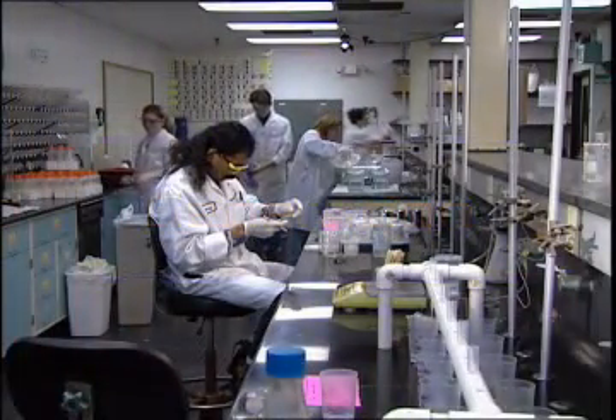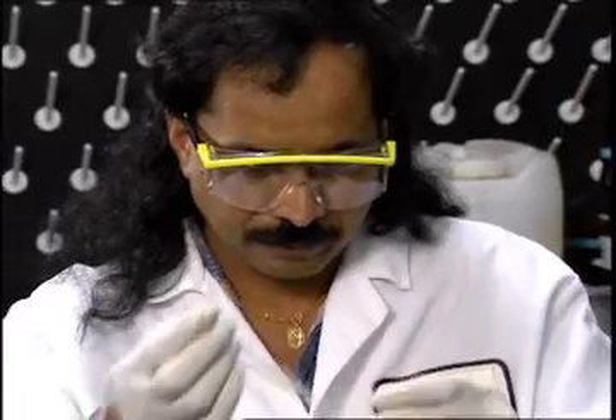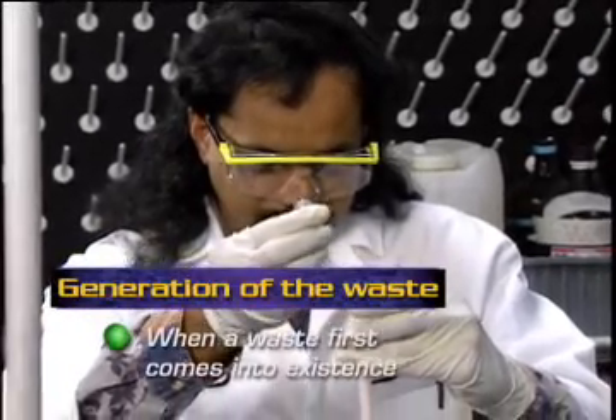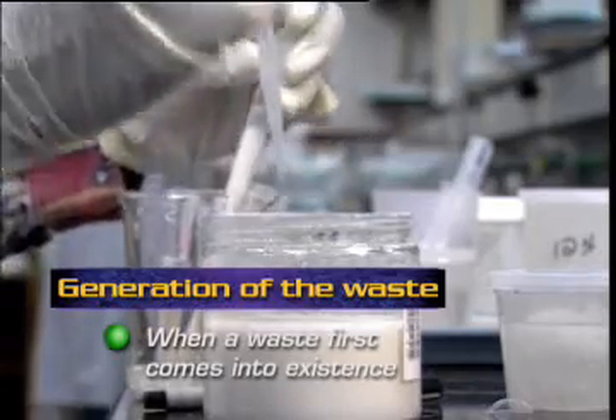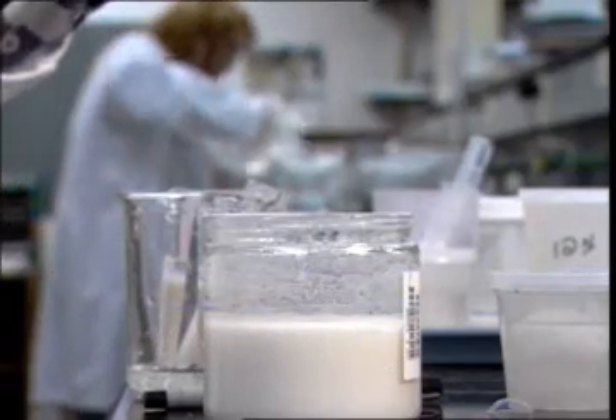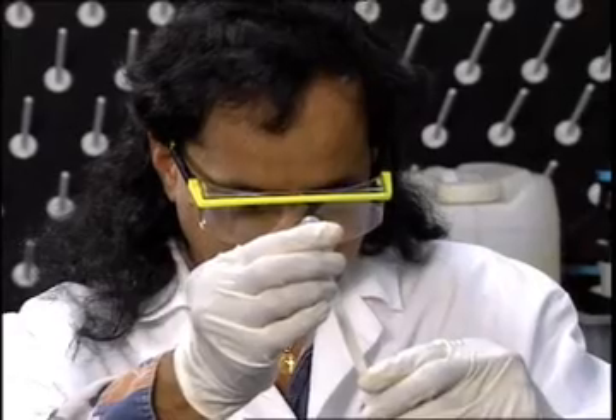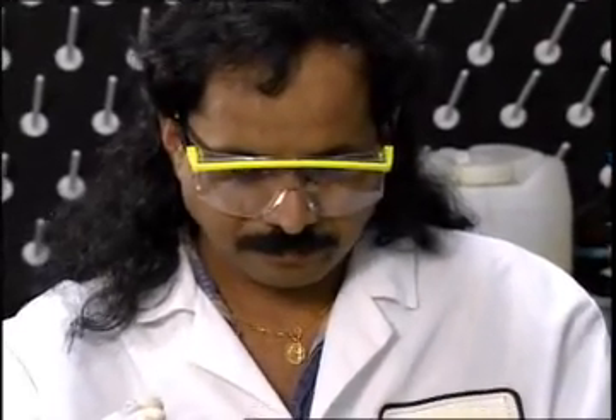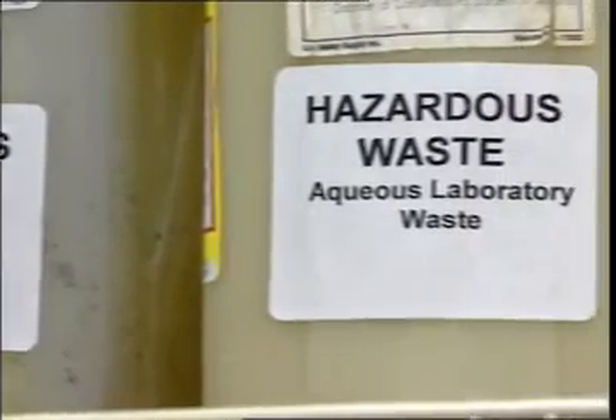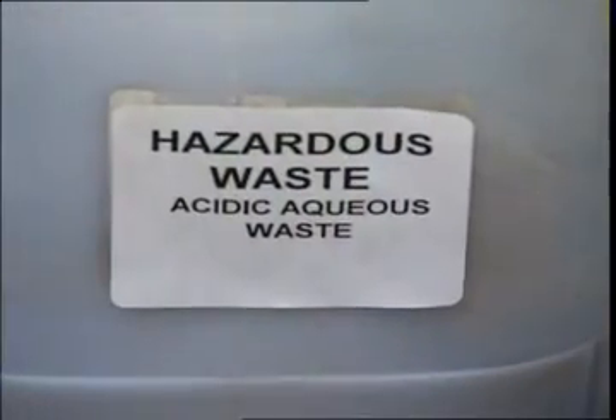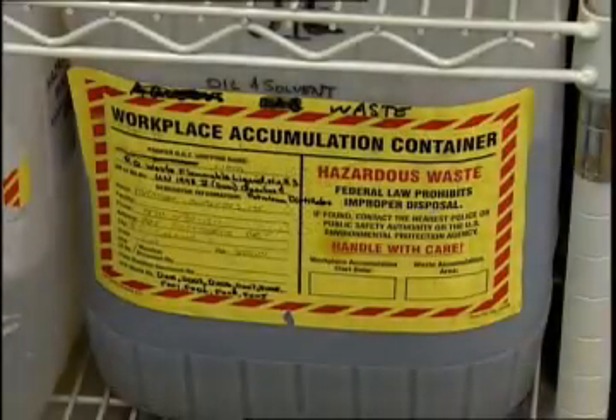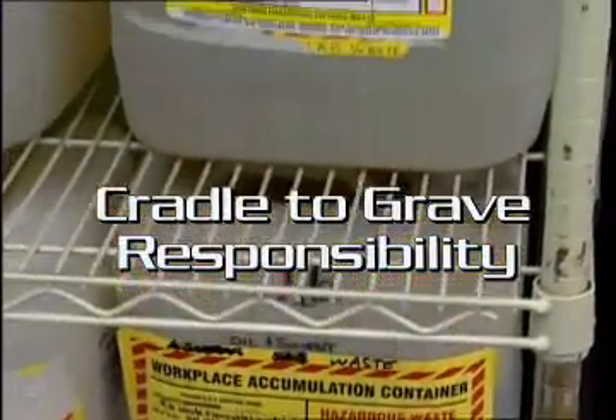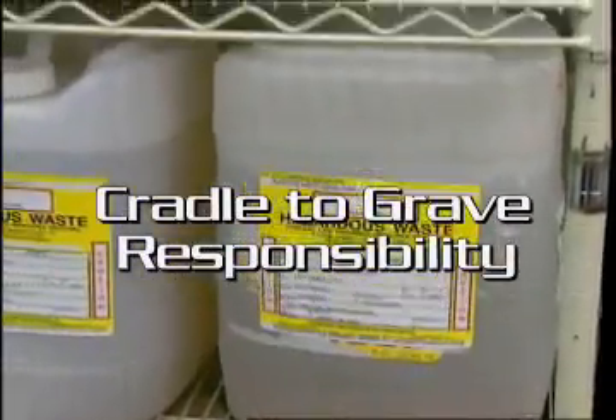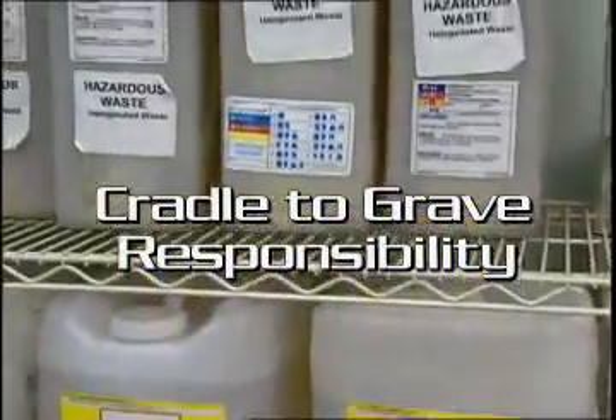When a waste first comes into existence, in a test procedure, experiment, or a sample analysis, or as a result of a spill or an accident, this is termed generation of the waste. When a waste is first generated, it must be determined if that waste is hazardous. Once generated, a hazardous waste becomes the facility's responsibility for as long as that waste exists. The EPA calls this cradle-to-grave responsibility. The facility never loses responsibility for its waste and never totally transfers its liability to another party, not even the off-site facility that will ultimately treat or dispose of the waste.